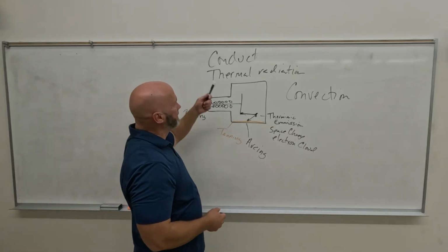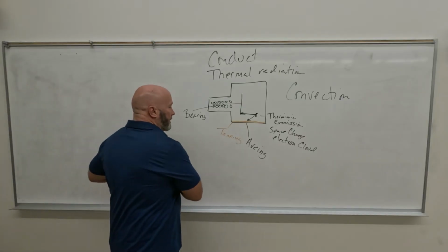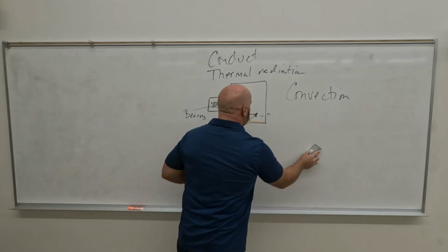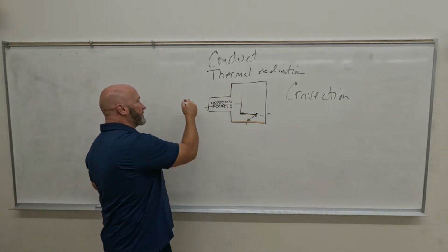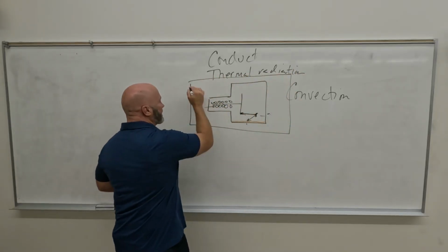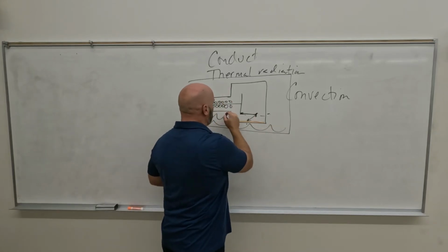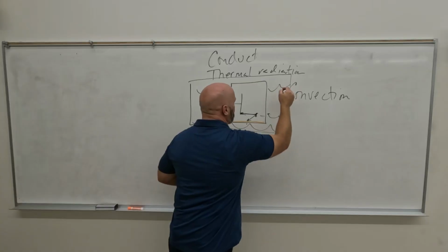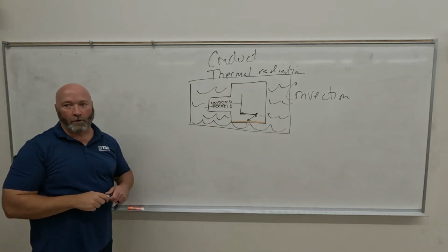Well, we kind of dealt with conduction to a degree. We're going to get rid of all this and just remember tube failures because of heat. You don't see the x-ray tube because it's in what we refer to as a protective housing. That protective housing is full of oil. And I pronounce it that way specifically because I've got listeners in other countries that don't know what oil is.